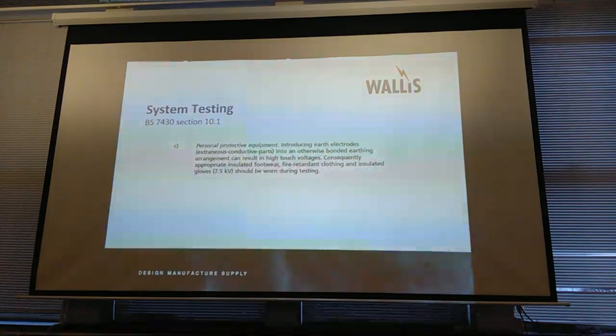System testing, 7430 actually stipulates personal protective equipment: introducing earth electrodes into an otherwise bonded earthing arrangement can result in high touch voltages. Consequently, appropriate insulated footwear, fire retardant clothing and insulated gloves, 7.5 kV, should be worn during testing. Now, that's as much as that says. It doesn't go into any great detail about that. But for me, if you have, and again, I'm working on personal experience here.